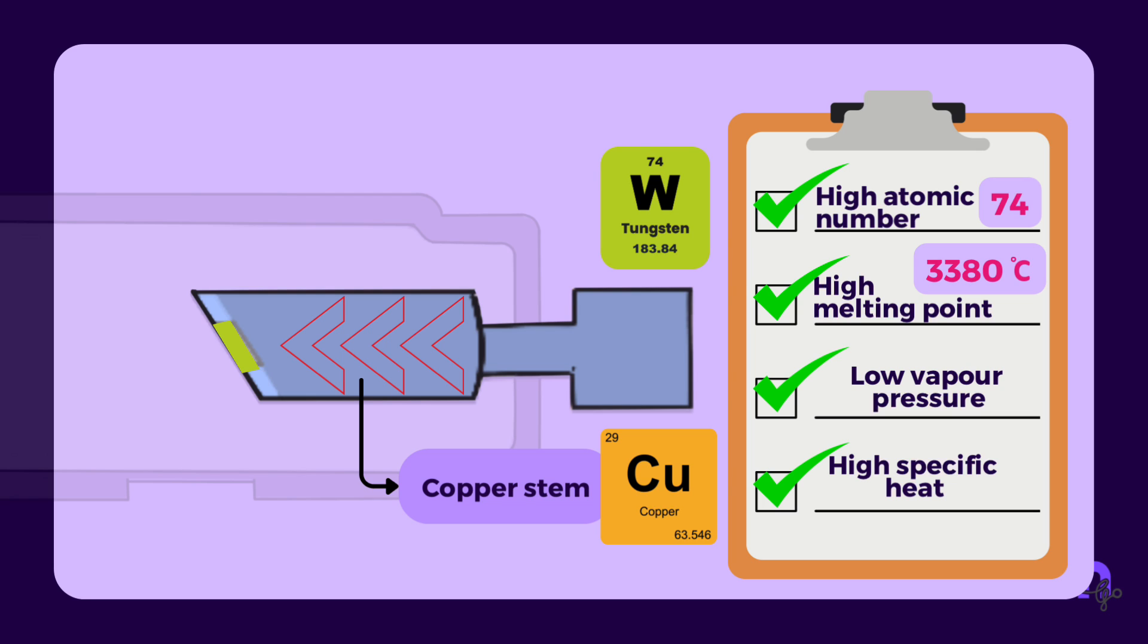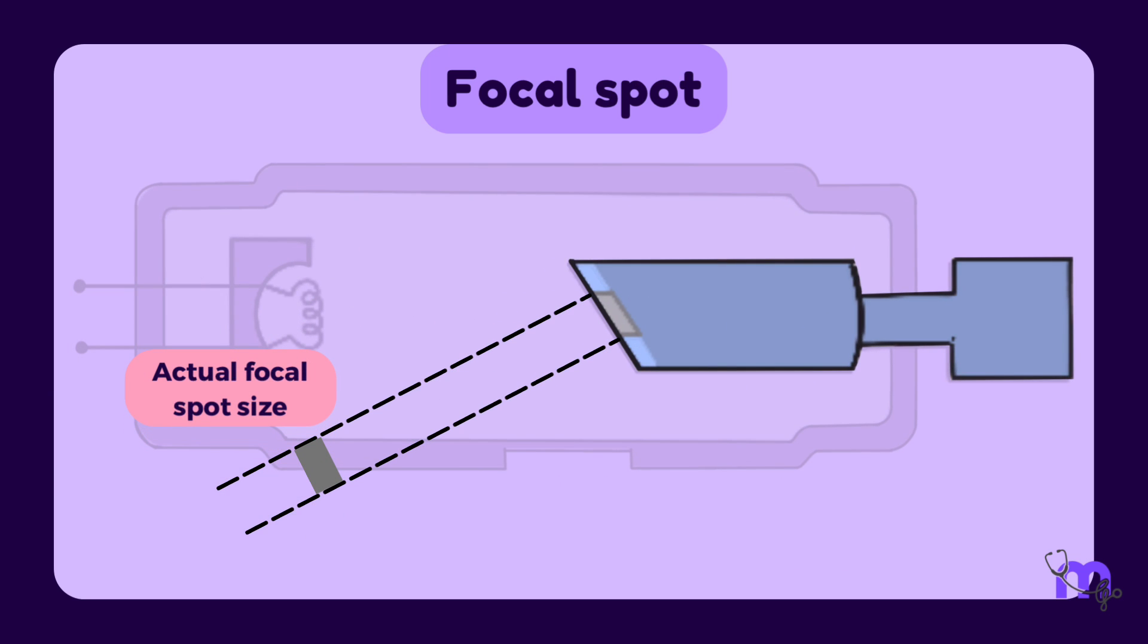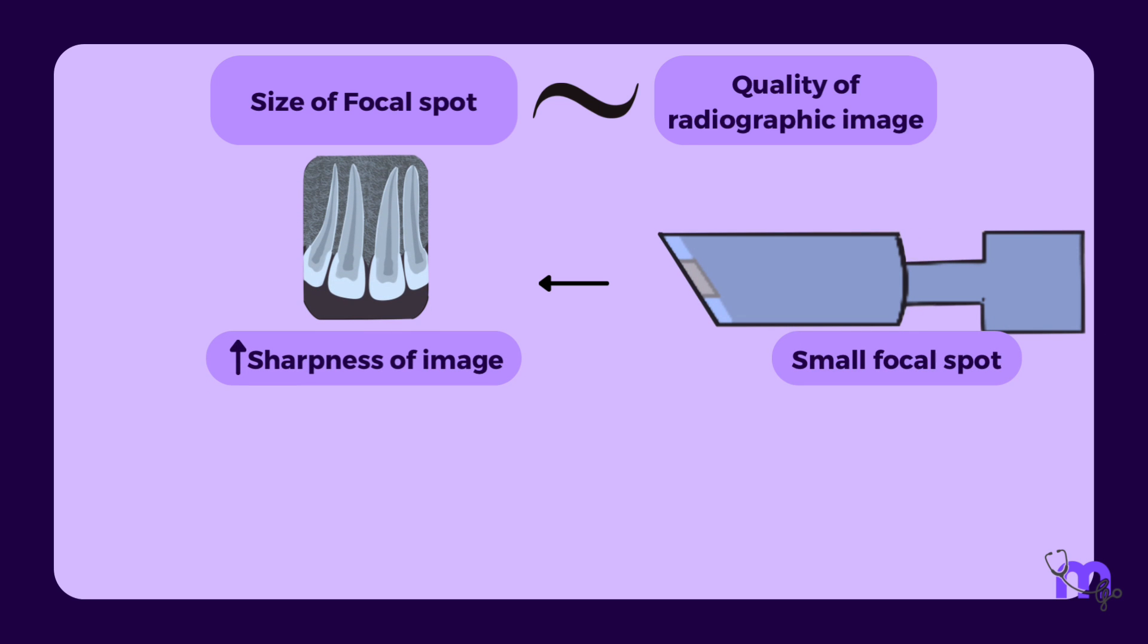Let us now discuss a very important area of the anode called the focal spot. This is a region on the tungsten target onto which the focusing cup directs the electrons. The actual size of the focal spot is one millimeter by three millimeter. We must keep in mind that the size of the focal spot influences the quality of the radiographic image. This means a small focal spot increases the sharpness of the image.